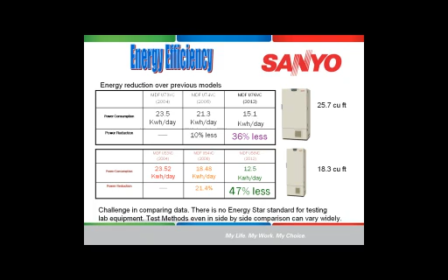Some of the most challenging things manufacturers have is dealing with heat exchangers rather than trying to go to smaller compressors to provide the same cooling capacity. The reason I'm comparing to ourselves is that we are finding that there are very widely ranging numbers that we're seeing specified throughout the whole market as far as what the energy consumption of freezers are. Part of that is because there is no Energy Star standard for testing lab equipment. Many of us were involved in this trying to come up with a standard, and we so far have unfortunately failed at that. But as I mentioned this morning, I just had a long conversation with the Department of Energy that is looking forward to moving in the direction of making sure there's a unified standard very similar to what the Energy Star program is.